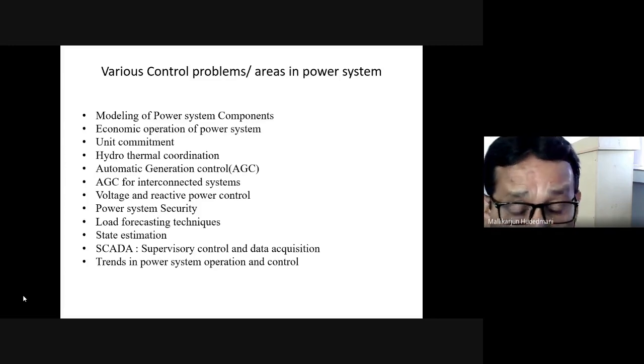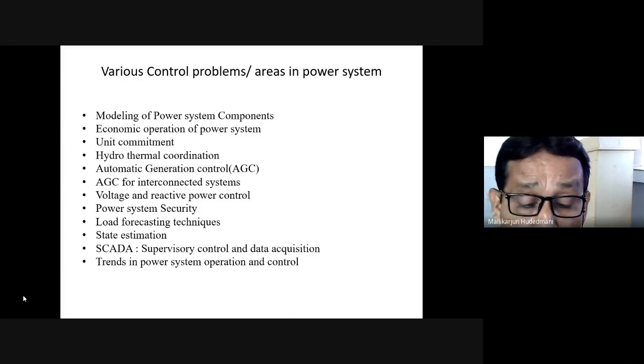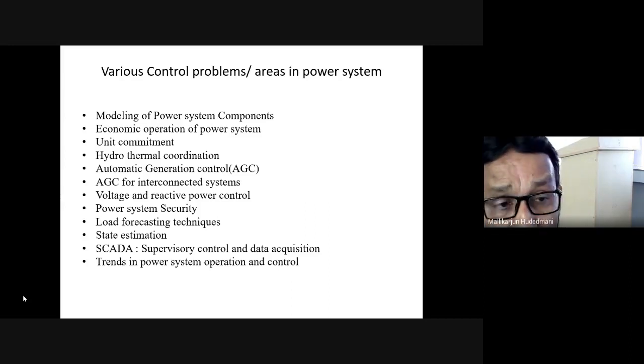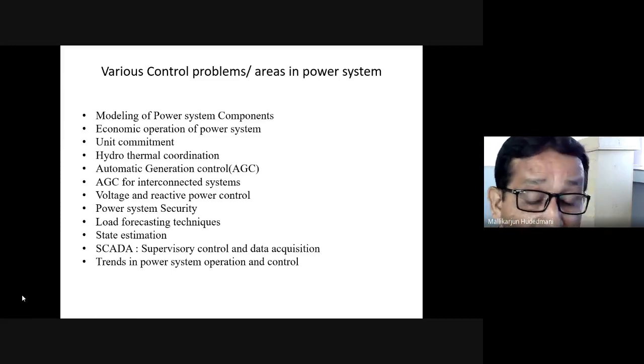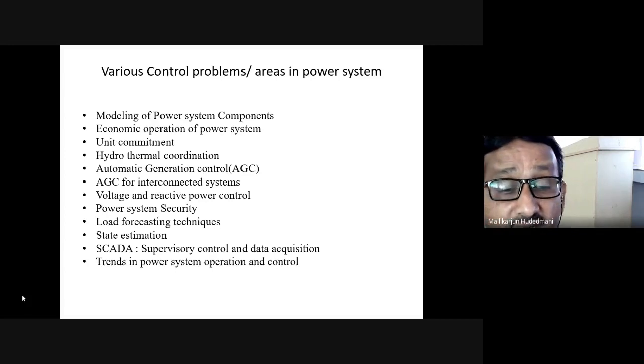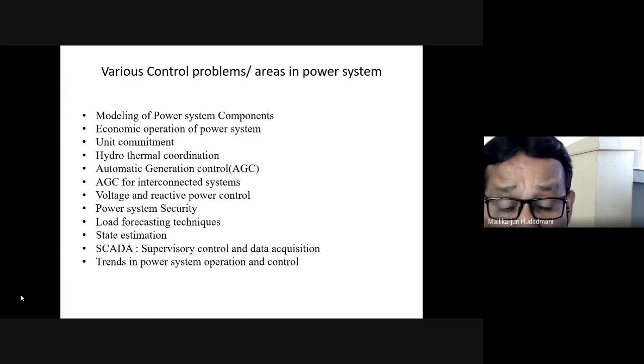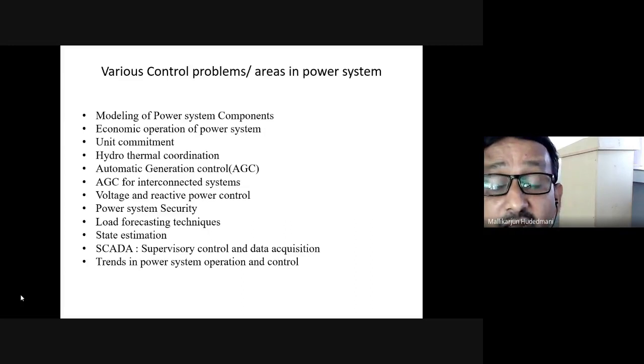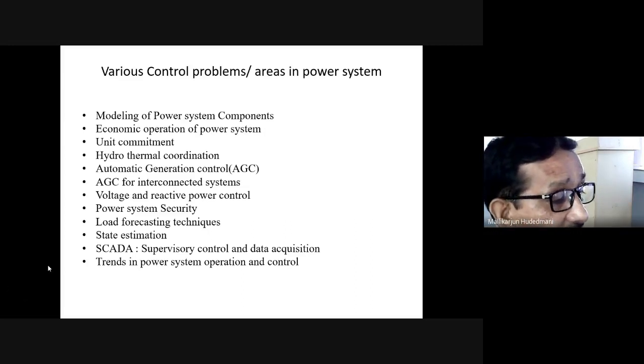We will learn this in another chapter. Voltage collapse is a very serious phenomenon. As load growth occurs, it hits active and reactive power demands. If the system cannot respond similarly, voltage collapses. The relation between incremental change in megawatt and megavolt-ampere-reactive versus the fall of voltage is plotted as a curve, which shows a tremendous fall of voltage for a minor increment in active and reactive power. So control of these is very crucial and important.